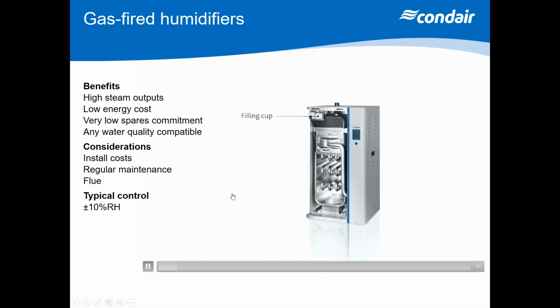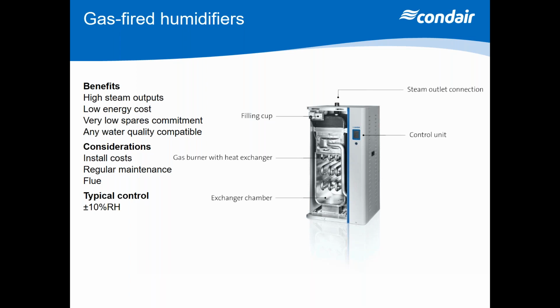Now, you can have a gas-fired humidifier. It's not just the electric humidifiers you can have there. This is a gas-fired humidifier. And here, simply, we have a boiling chamber that will fill with water that's attached to a heat exchanger that's immersed in it as an immersed heat exchanger. And that heat exchanger is attached to a burner, and we fire hot gases into the heat exchanger and heat the water up and produce steam at atmospheric pressure.